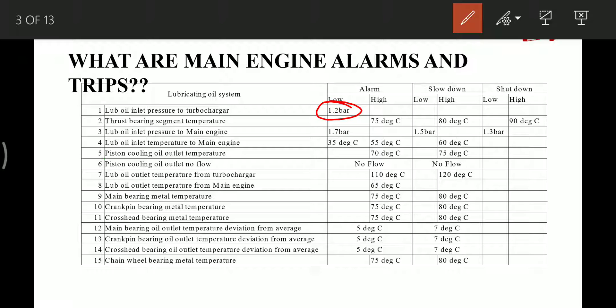Thrust bearing segment temperature is very important as it has alarm, plus shutdown, plus slowdown. At 75°C it gives a high temperature alarm. At 80°C it slows down the main engine, and at 90°C it shuts down the main engine.